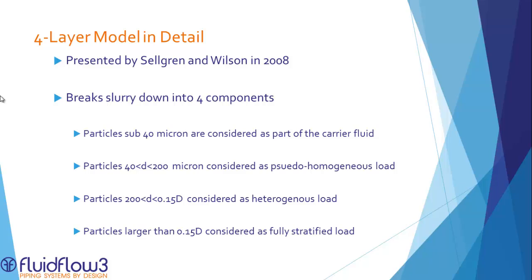The four layer model was presented by Selgren and Wilson in 2008. The model works by breaking the slurry down into four components. Particles sub 40 micron are considered to be part of the carrier fluid. Particles between 40 micron and 200 micron are considered as a pseudo-homogeneous load. Particles between 200 micron and 0.15 times the pipe diameter are considered as heterogeneous load. Particles higher than 0.15 times the diameter are considered fully stratified.